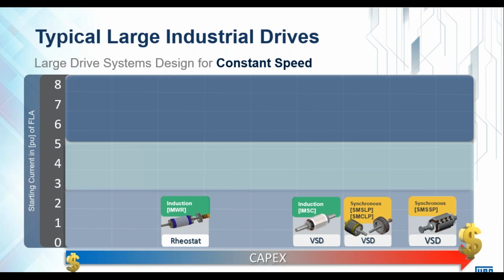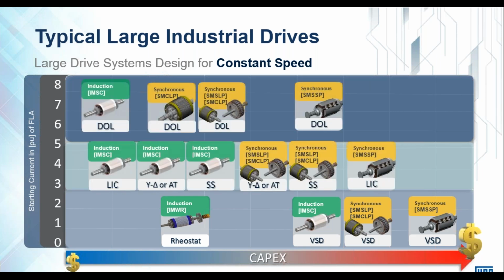Right, then we do the same or similar summary of starting current versus capex for the different impacts onto the power system. So the lowest impact designs would be a wound rotor induction motor coupled with a rheostat. That would be the least expensive option for low impact to the power grid. A VSD, if not used for continuous speed variation, is quite obviously a lot more expensive. However, you do get the added advantage that you can use it with a squirrel cage machine. And so from an OpEx point of view on the motor itself, it is reduced compared to a slip ring machine.